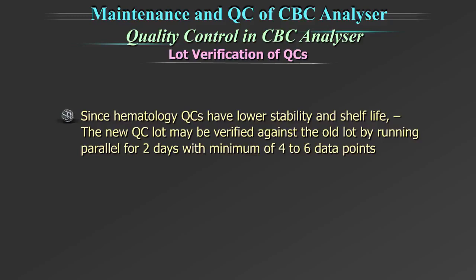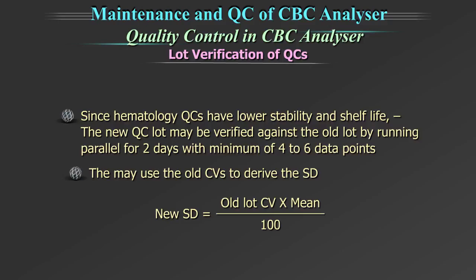The new quality control lot may be verified against the old lot by running parallel for 2 days with a minimum of 4 to 6 data points to get the mean. They may use the old CVs to derive the standard deviation using this formula. New lot SD, or standard deviation, is equal to the old lot CV times the mean of the new QC runs divided by 100. Please refer to Quality Control module of the L4L for further details.